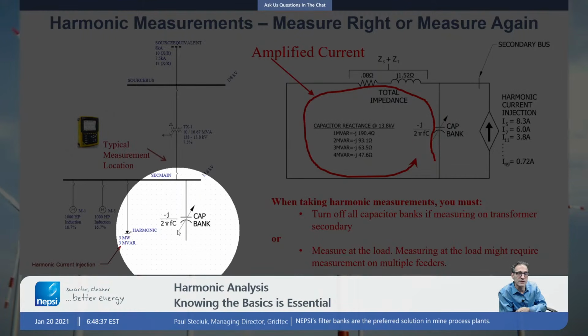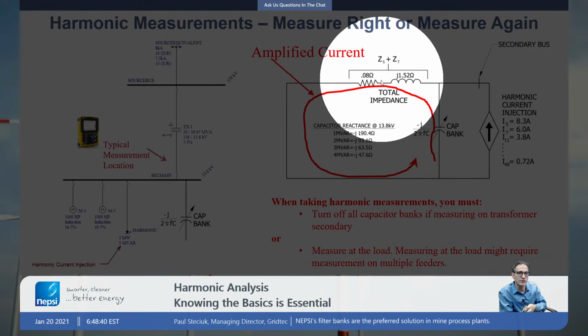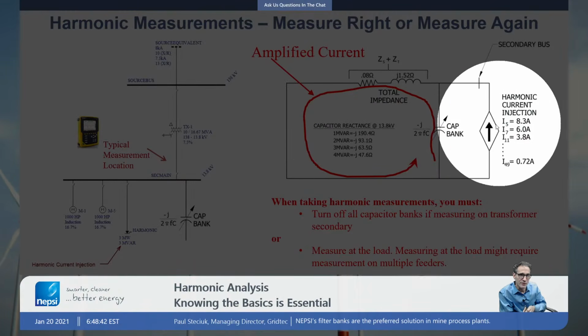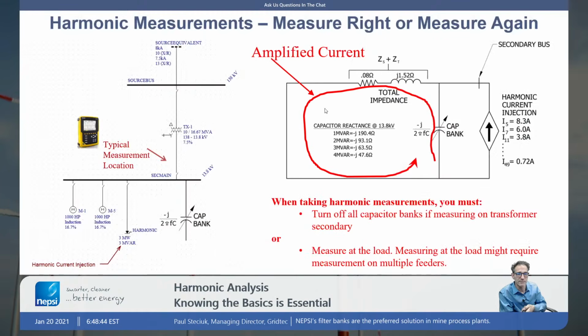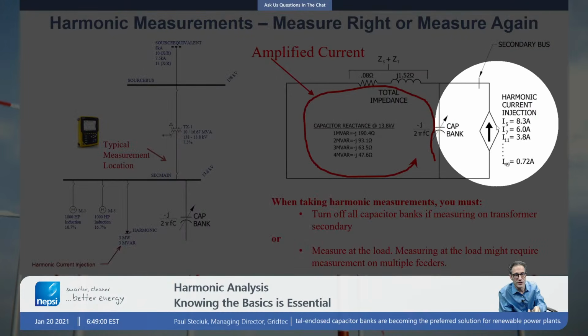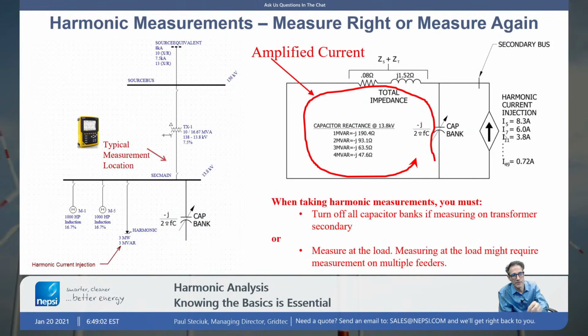If the capacitor bank is on, the value of current that you're measuring is not the current injection, it's the amplified value. And it becomes useless. You can't use that in harmonic analysis. So if there's consideration being given to adding capacitors to a network or making changes to the network and you're looking to do a harmonic analysis, the harmonic analysis input is a harmonic injection value. It represents the drive output current, all the nonlinear load current within the plant. What is that value of current that you have?